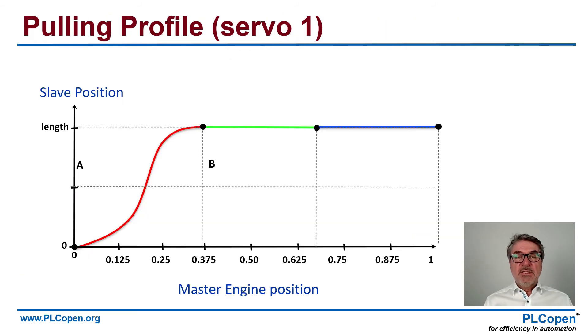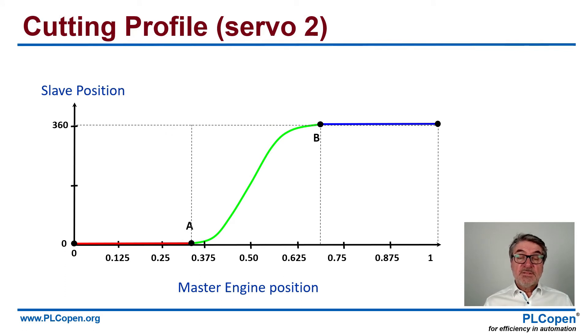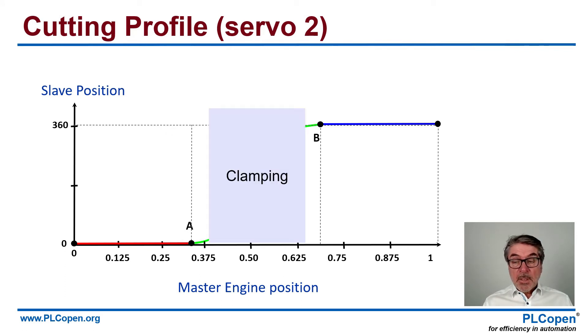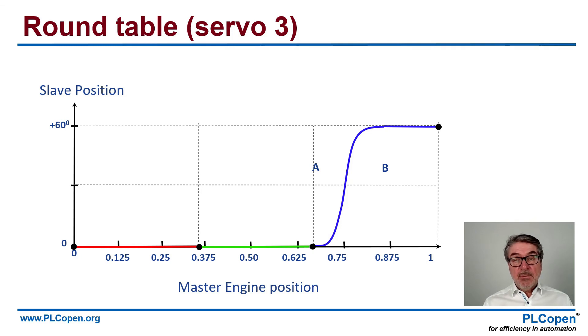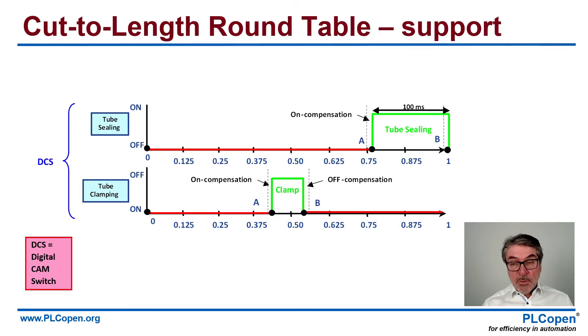If we look at the profiles we use: for servo one, we unwind the tube — we see a master versus a slave, and the slave goes to the required length of the tube. The cutting is servo two. Part of that is dealing with the clamping, so we link that to a clamping functionality. The third one is the round table — if the tube is on there, we turn it one tick of a full round, and the workstation works on that part — for instance, tube sealing as the first step. This is supported with clamp functionality on the bottom and tube sealing on the top, which is on the table itself.